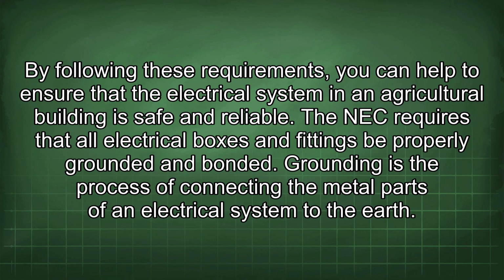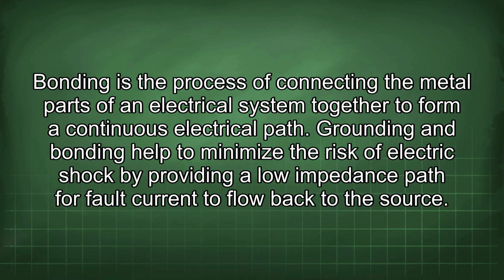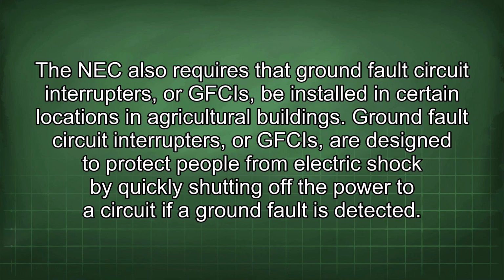The NEC requires that all electrical boxes and fittings be properly grounded and bonded. Grounding is the process of connecting the metal parts of an electrical system to the earth. Bonding is the process of connecting the metal parts of an electrical system together to form a continuous electrical path. Grounding and bonding help to minimize the risk of electric shock by providing a low impedance path for fault current to flow back to the source. The NEC also requires that ground fault circuit interrupters, or GFCIs, be installed in certain locations in agricultural buildings. Ground fault circuit interrupters, or GFCIs, are designed to protect people from electric shock by quickly shutting off the power to a circuit if a ground fault is detected.